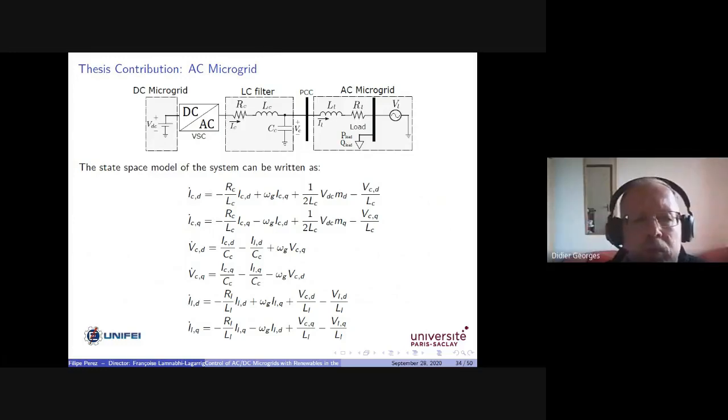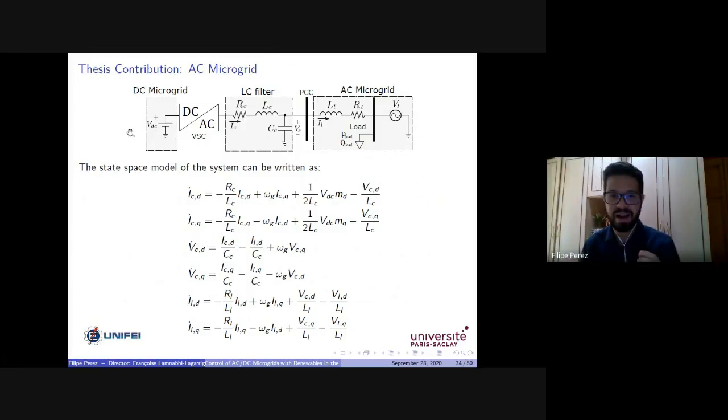Okay. And when you consider connection to an AC power system, since your goal is also to be connected to AC systems, what kind of model do you use for representing the AC power systems? We are representing the grid as a dynamic with a capacitor voltage. When modeling a strong grid, you use the voltage as a voltage source, so it's not a state variable. When we are modeling a weak grid, the capacitor voltage is used as a state of the model.